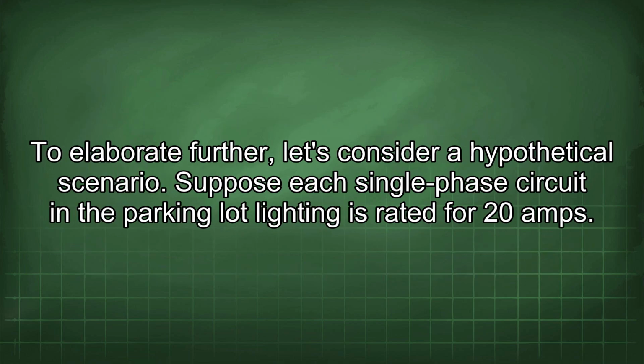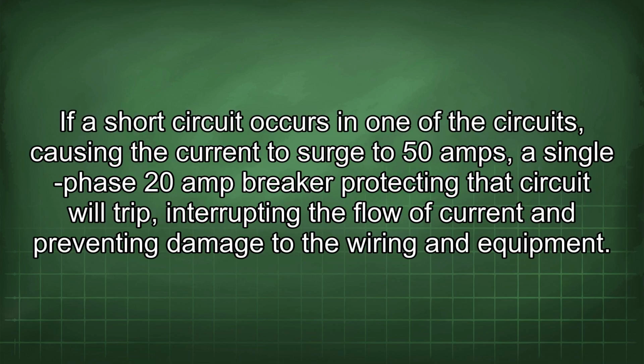To elaborate further, let's consider a hypothetical scenario. Suppose each single-phase circuit in the parking lot lighting is rated for 20 amps. If a short circuit occurs in one of the circuits, causing the current to surge to 50 amps, a single-phase 20-amp breaker protecting that circuit will trip, interrupting the flow of current and preventing damage to the wiring and equipment.